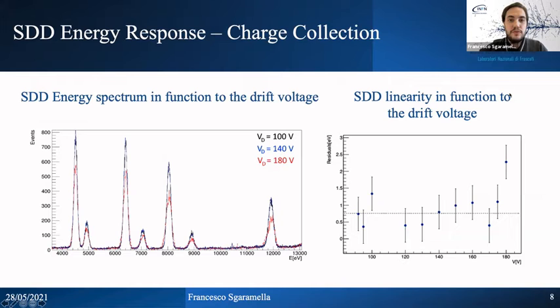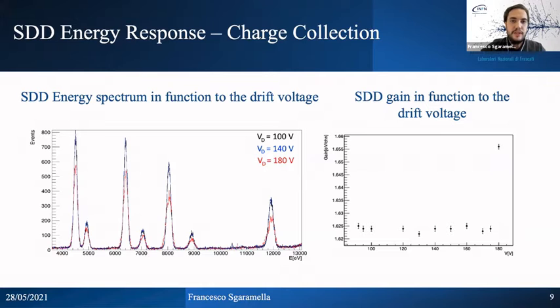In this figure, the figure shows the overlap of the spectra acquired at 100, 140 and 180 volt. There are no differences, as you can see, in the spectra acquired at 100 and 140 volt. Instead, at 180 volt, there is a consistent decrement in the amplitude of the peaks due to a widening of the peaks. On the right, I reported the mean residual value as a function of the drift voltage. The response of the detector is still linear within a few electron volts, but the gain of the linear function increases, moving from 100 volt to 180 volt.